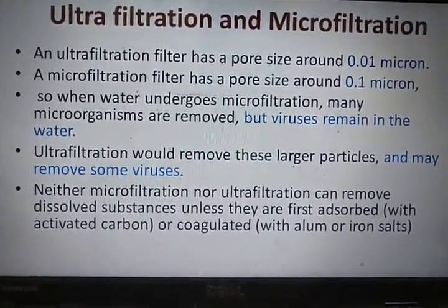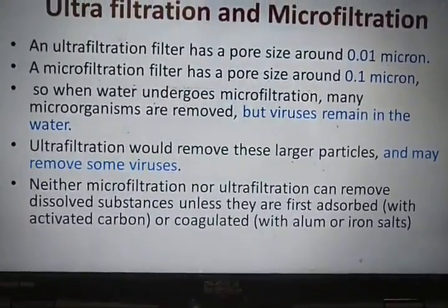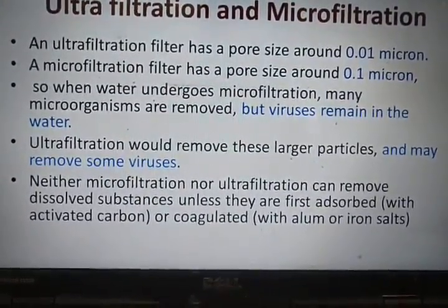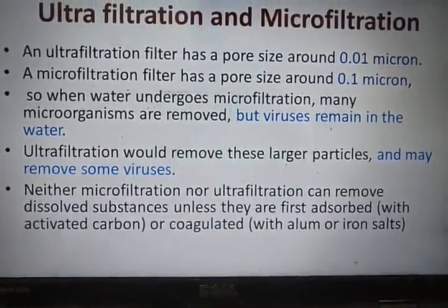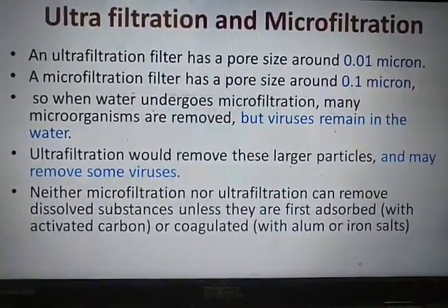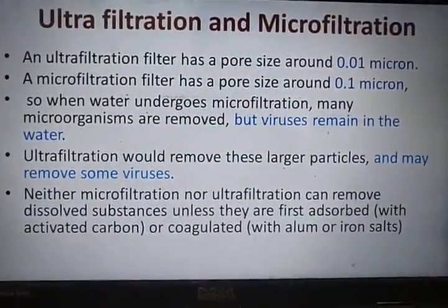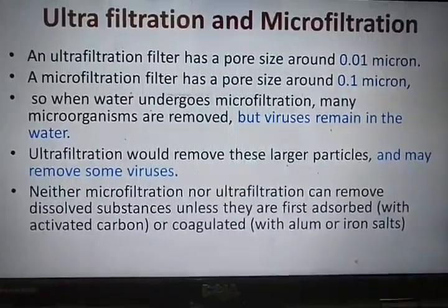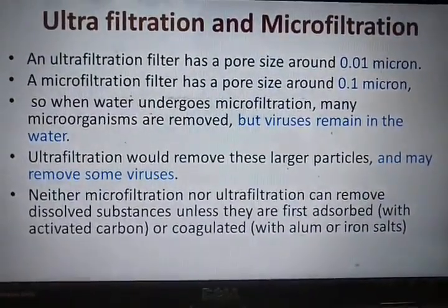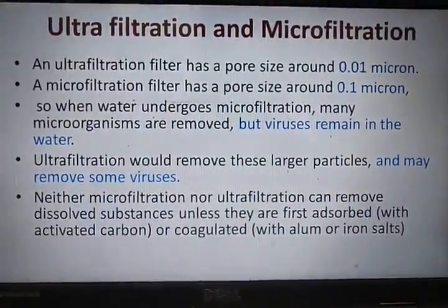Neither microfiltration nor ultrafiltration can remove dissolved substances unless they are first adsorbed with activated carbon or coagulated. Here, please note that these membranes will not remove the dissolved substances. Like water may contain some dissolved solids in the form of carbonates of calcium and magnesium, which cause hardness, then these membranes are not able to remove those kinds of dissolved substances.